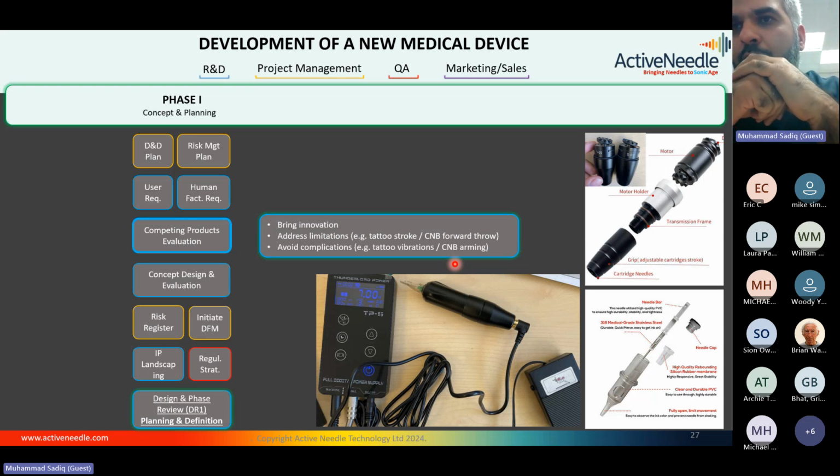One of the things that we came across with our biopsy device, for example, is that conventional biopsy devices, some of them are automated. So you go very close to your target, and when you press the button, it throws the biopsy needle, the sample collection needle, forward. If you cannot see the needle very well, it can actually hit surrounding tissues and damage nerves as well.